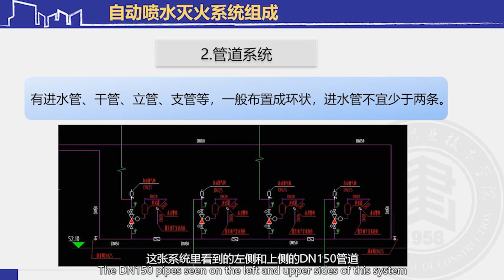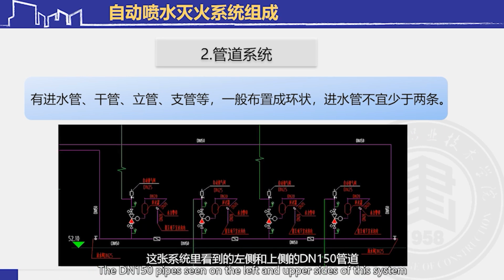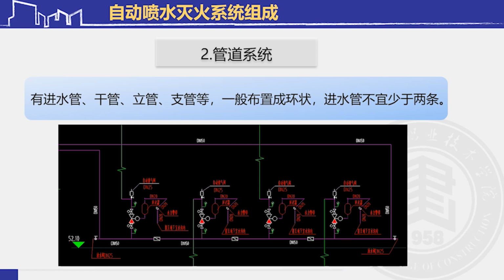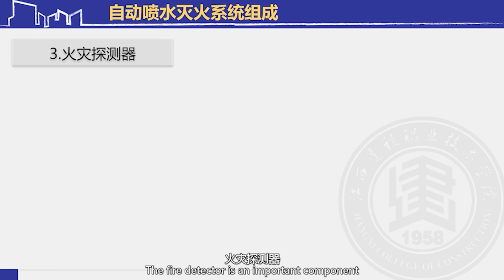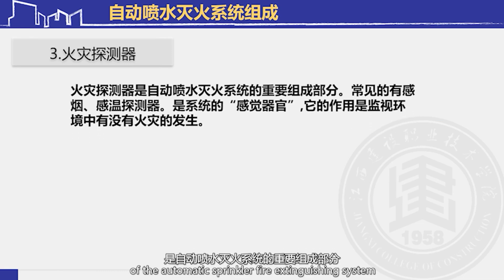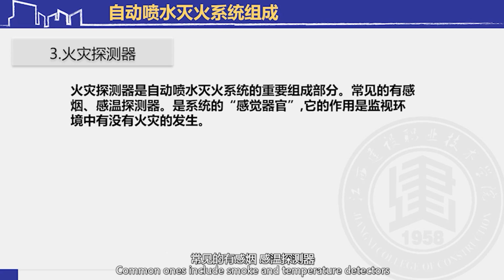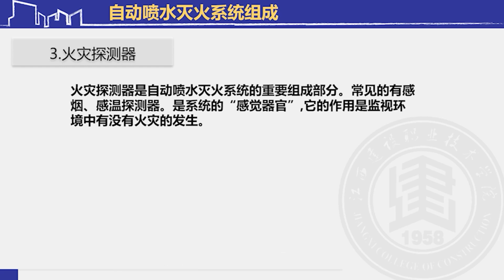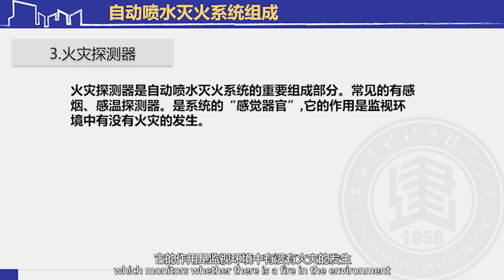The DN150 pipes, seen on the left and upper sides of this system, are the 2 inlet pipes of the sprinkler system. The fire detector is an important component of the automatic sprinkler fire extinguishing system. Common ones include smoke and temperature detectors. It is the sensory organ of the system, which monitors whether there is a fire in the environment.